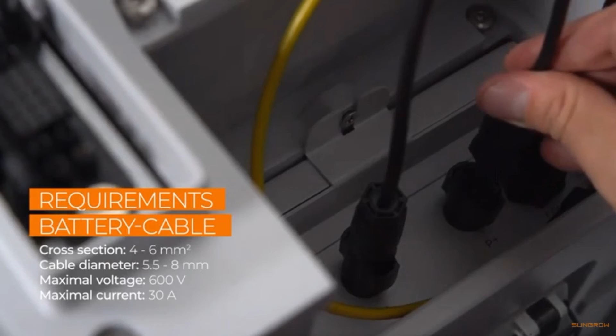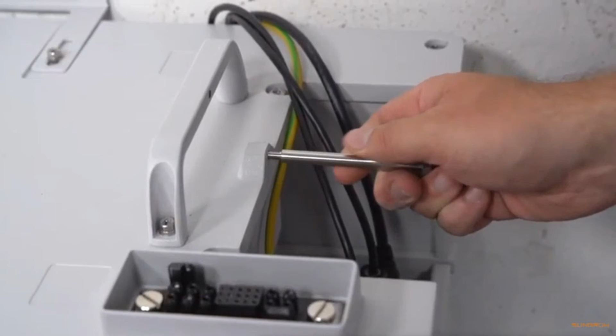Connect the battery power cables to the P- and P+ port on the battery side. In the next step, the cables also need to be connected to the three-phase hybrid. Fix the switchgear with the stud, which is part of the delivery scope. Make sure that all cables are correctly positioned to fit into the intended recess in the cover of the battery. Place the cover on the battery and fix it on both sides with the included M5 screw. Clip in the side cover. That's it, quick and easy, beyond the expected.